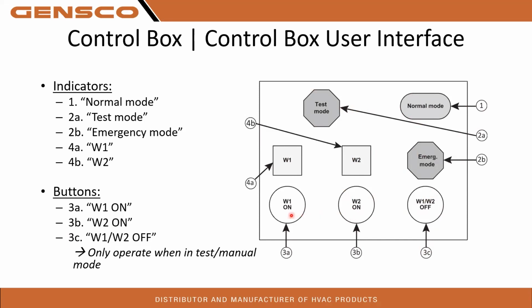On the control board, on the relay board, there is a SW01 dip switch bank. When using that, you will be able to test the gas furnace operations by initiating test mode. Again, the only operation you're going to be able to do is test mode, and it's either going to be first stage heat, second stage heat, or turn them both off. These up here are all just LEDs indicating what mode it's in, whether it's normal mode, test mode, or emergency mode.